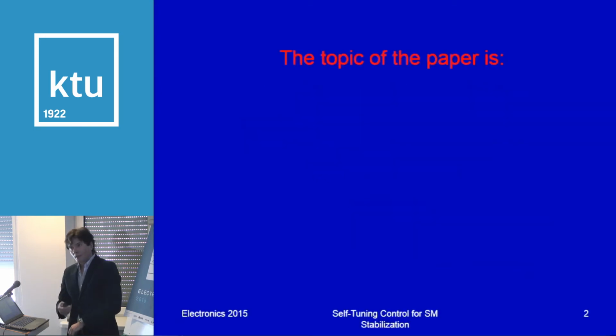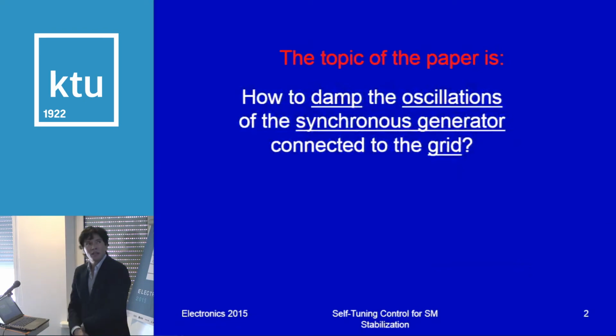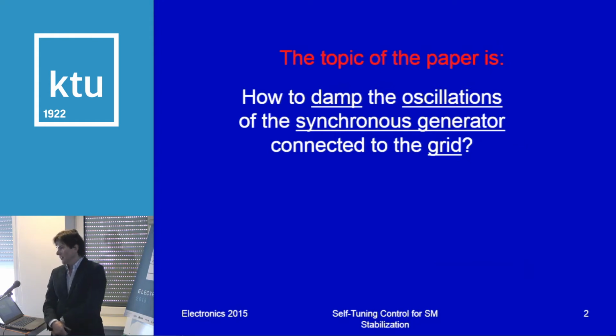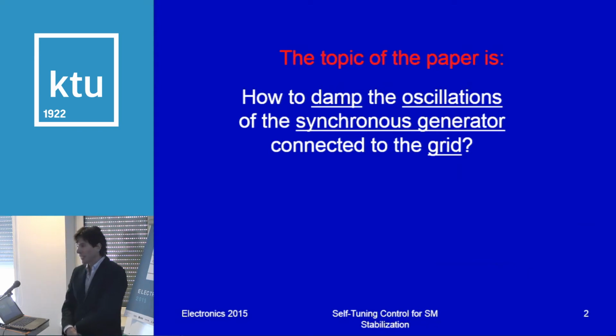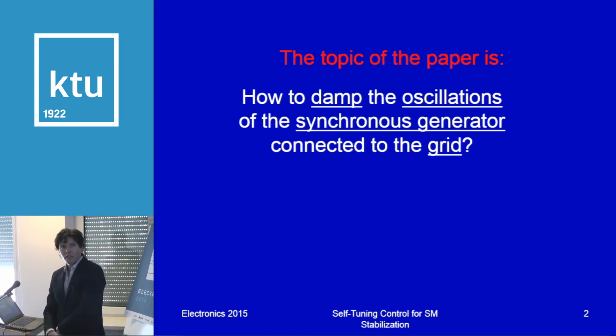If I would like to present the topic of the paper in one sentence, it is how to damp the oscillation of a synchronous generator connected to the grid. I will speak about conventional synchronous generators used in power plants, with nominal powers from 10 kilowatts up to 2000 megawatts. These produce more than 99% of total electrical energy. They are very nonlinear dynamical systems with two inputs, so we need two additional devices for operating. One input is the mechanical torque produced by a water or steam turbine, and the second is the rotor voltage that generates the magnetic field in the machine, produced by the excitation system.